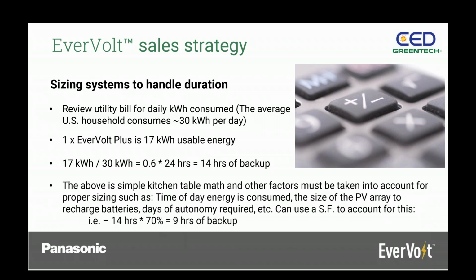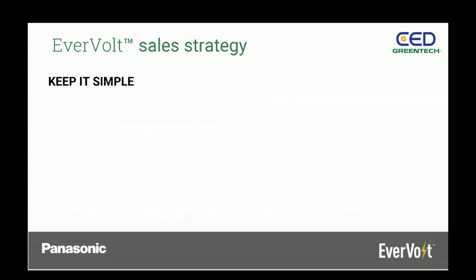Now, you want to build a huge buffer into that because there's a lot to consider beyond that: time of day the energy is consumed, the size of the PV array to recharge the batteries, the days of autonomy required. The safety factor we throw out there is 70%. So you take that 14 and it reduces down to 9 hours. Again, this is just quick and dirty kitchen table math, but you want to go as deep as you can for that customer to make sure the system is correctly designed for their expectations.